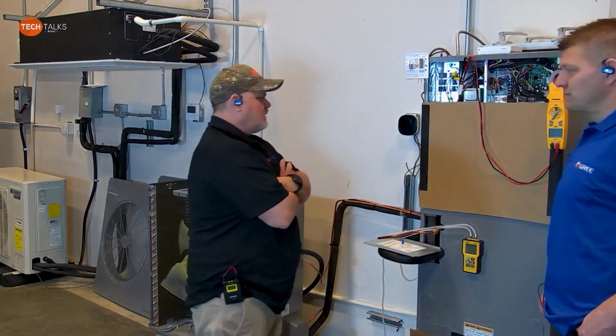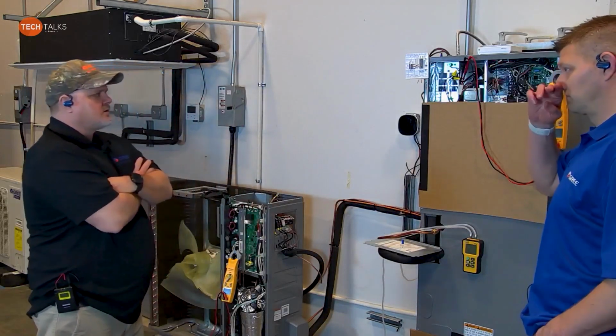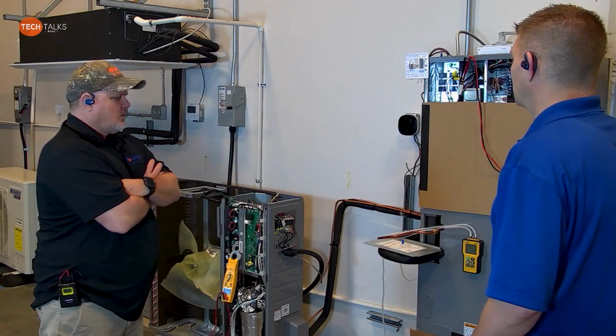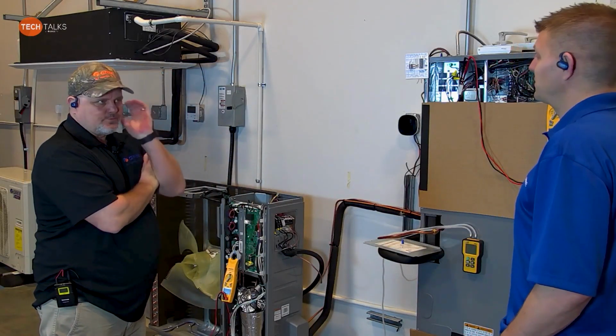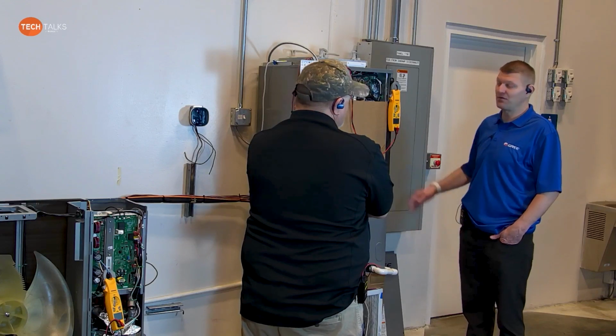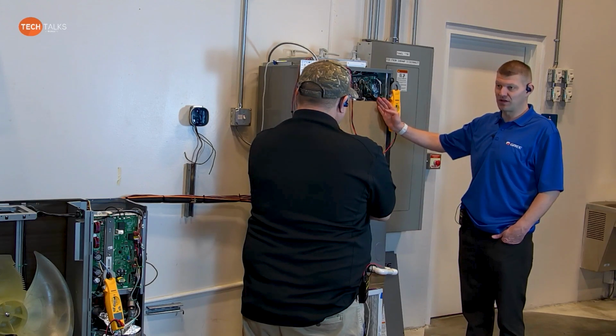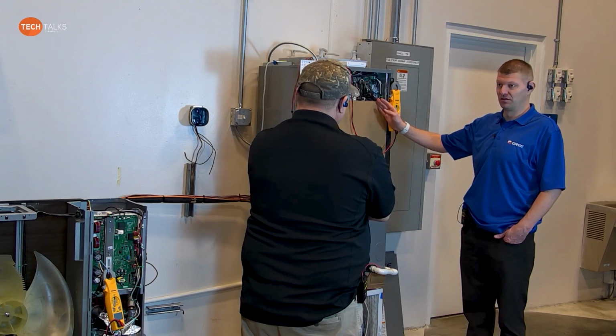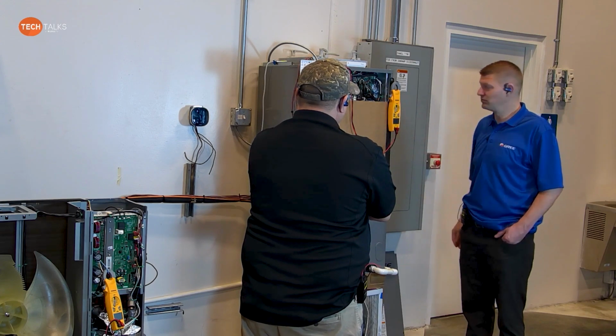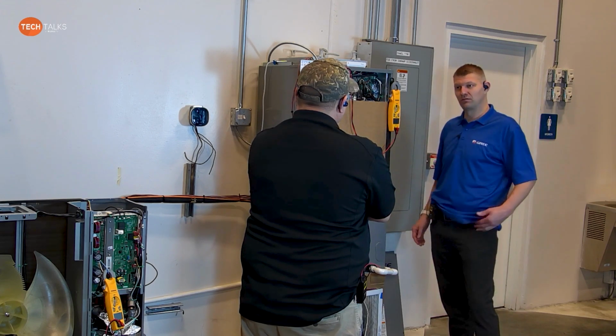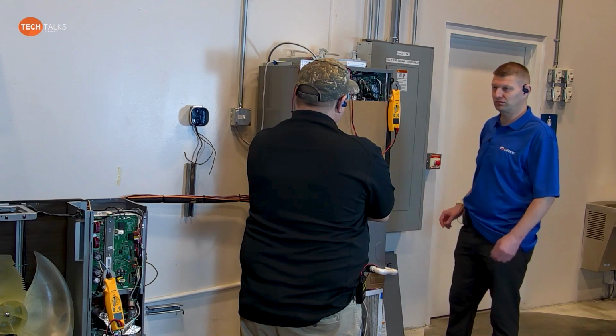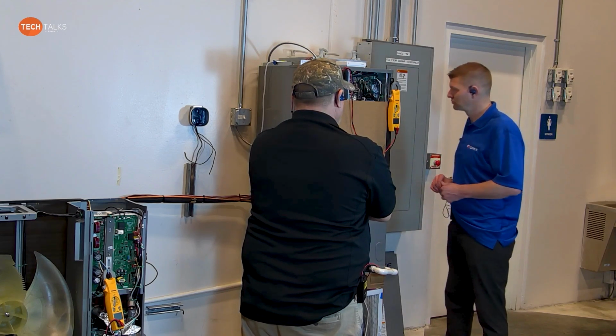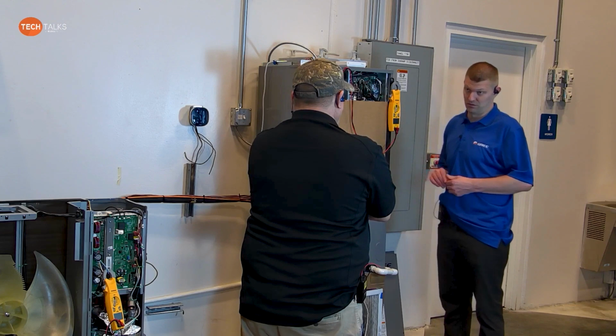So JD, refresh my memory here. Do we have this thing set up right now for 24 volt? Or do we have it set up for the GREE control? So it is set up for 24 volts. To do that, we had to adjust the dip switch on the indoor unit, SA1. Dip switch number 1 has to be turned on. Okay. And so SA1, just to refresh my memory, those are heating dip switches the way we always looked at it? Those are cooling. Those are cooling dip switches.